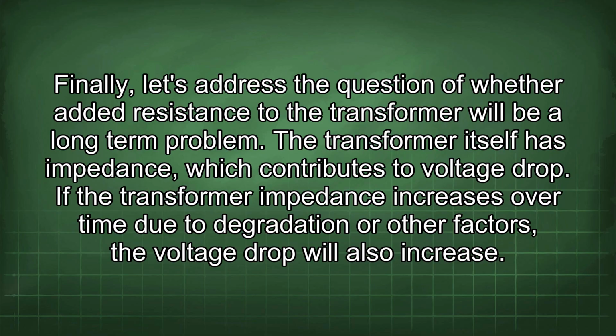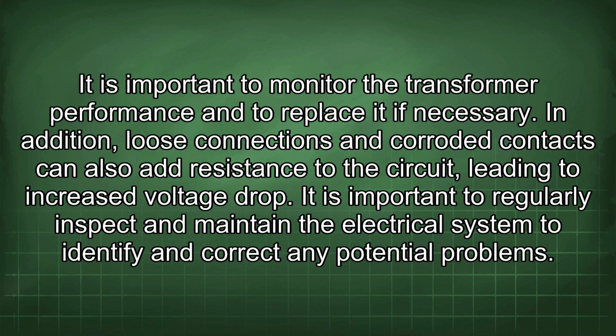Finally, let's address the question of whether added resistance to the transformer will be a long-term problem. The transformer itself has impedance, which contributes to voltage drop. If the transformer impedance increases over time due to degradation or other factors, the voltage drop will also increase. It is important to monitor the transformer performance and to replace it if necessary. In addition, loose connections and corroded contacts can also add resistance to the circuit, leading to increased voltage drop. It is important to regularly inspect and maintain the electrical system to identify and correct any potential problems.